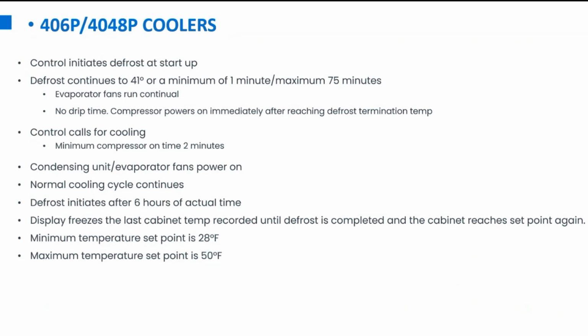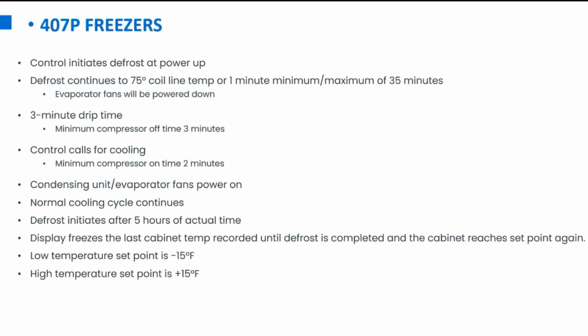All right, and then from there, also with the control, with the cooler, notice the minimum and maximum temperatures there. These can be set all the way up to 50 degrees or down to 28. As far as the freezers go, obviously a little bit different operation as we mentioned before. As far as the fans go, the fans will not run during defrost. So even though this unit has a hot gas defrost and the compressor is running, the evaporator fans do not run during the defrost. So they'll only run when the unit is calling for cooling.